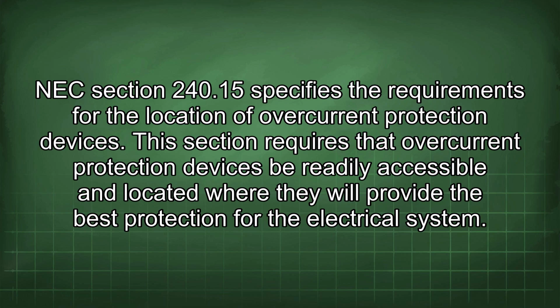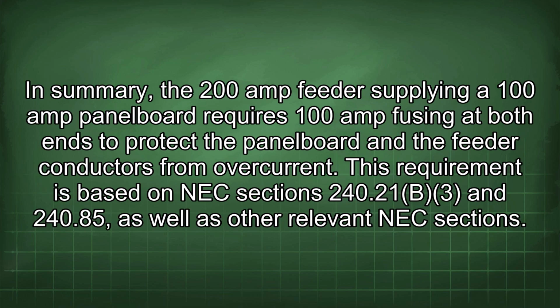This section requires that overcurrent protection devices be readily accessible and located where they will provide the best protection for the electrical system. In summary, the 200 amp feeder supplying a 100 amp panel board requires 100 amp fusing at both ends to protect the panel board and the feeder conductors from overcurrent. This requirement is based on NEC sections 240.21(B)(3) and 240.85, as well as other relevant NEC sections.